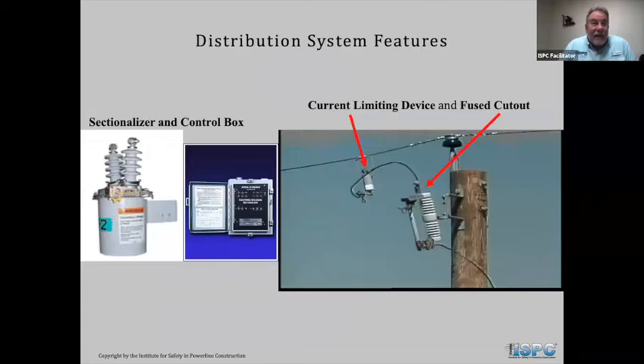All right, so then we spent a little time talking about sectionalizers, reclosers, cutout fuses. A lot of times, when you hear the explosion, like a rifle going off, a lot of people say, "Oh, the transformer blew," but actually, it was not a transformer; it was the fuse. And basically, it's just a small piece of wire going through as it overheats from an overvoltage or an overcurrent relationship. It would blow out the bottom of the barrel. So there's another hazard to your guys.